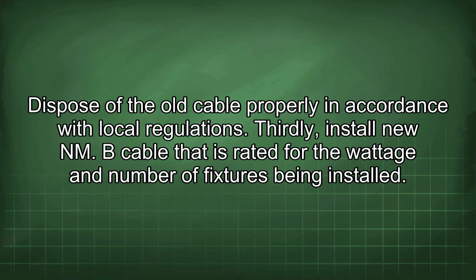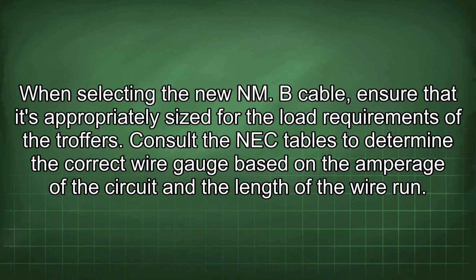Thirdly, install new NM-B cable that is rated for the wattage and number of fixtures being installed. When selecting the new NM-B cable, ensure that it's appropriately sized for the load requirements of the troffers.